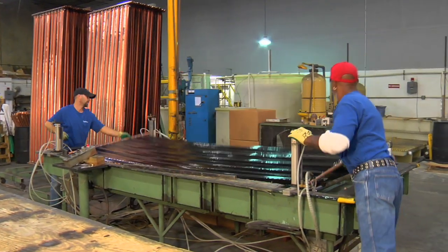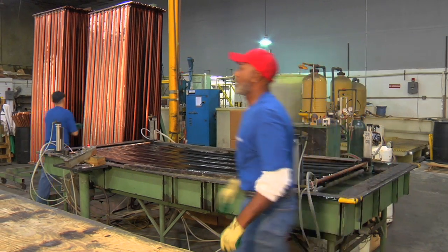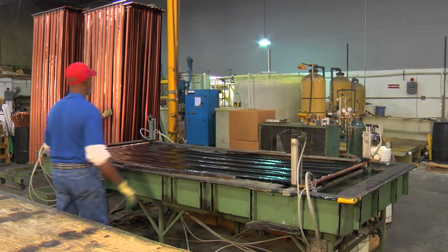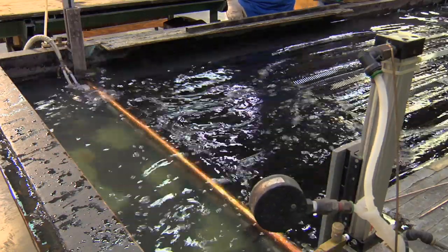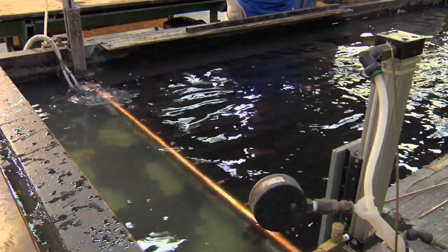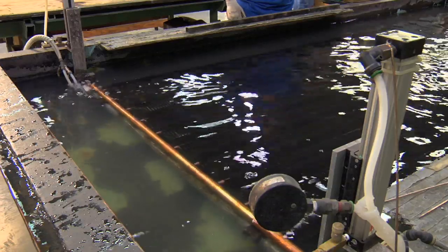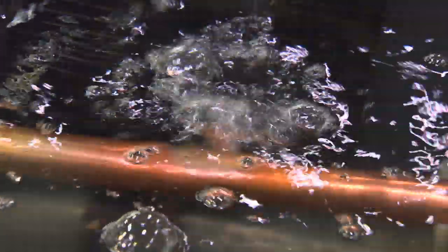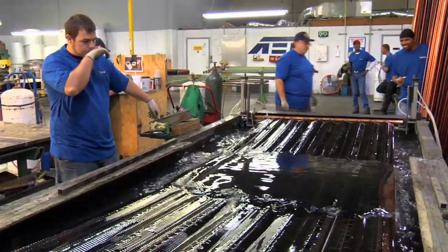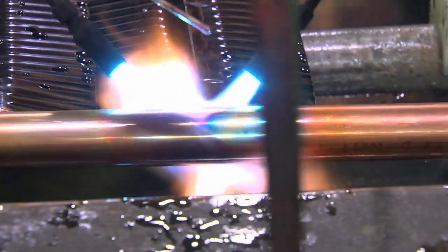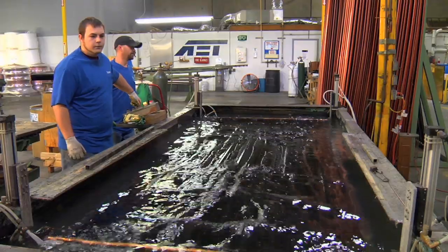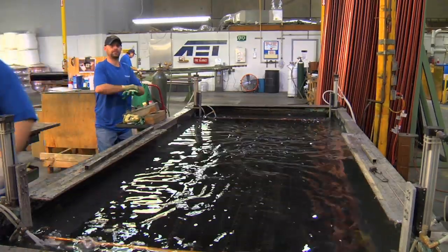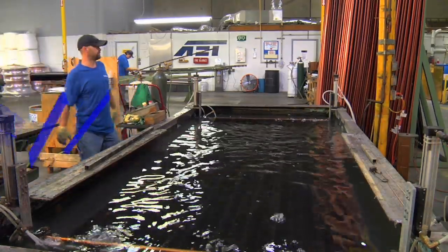Once completed, the absorber plate goes to a pressure check table. The plate is placed on the rack, the headers are clamped, and then it's immersed in water under pressure. The air valves are open to release air inside the absorber, while it's checked for leaks. Should air bubbles be present, the absorber is raised out of the water, and any leaks are repaired. Again, the absorber is immersed in the water and goes through the same checking process to ensure the integrity of the absorber plate.